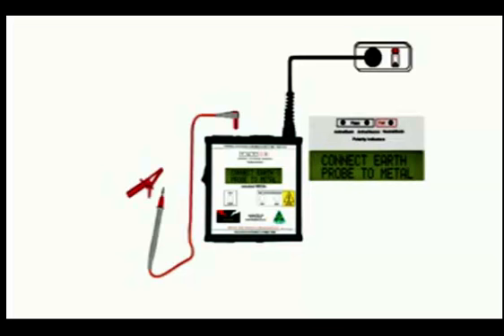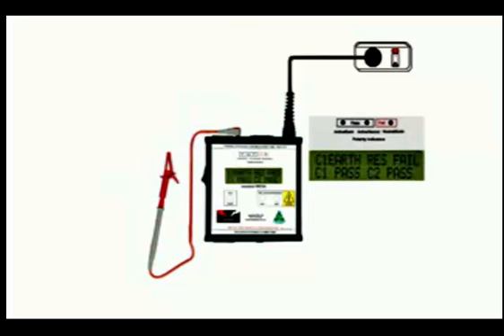You can see that the top line says we have an earth resistance fail. That's because there's no earth connected. In fact, the display will switch to tell you to connect an earth probe to the conducting part of the appliance to check this earth fault. Here's the probe. It's used to test earth integrity for Class 1 devices, and to provide an earth for Class 2 appliances to enable testing for leakage currents.